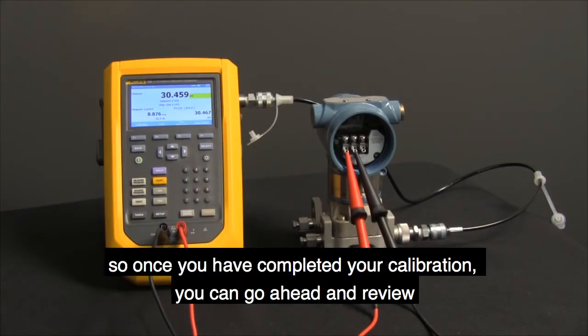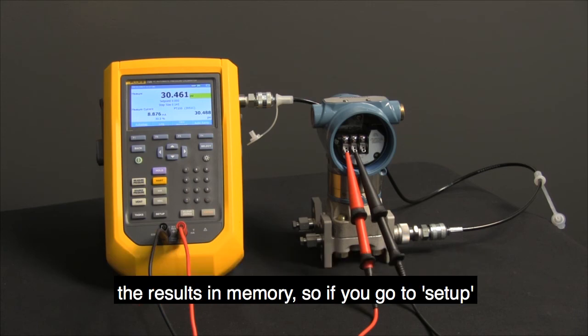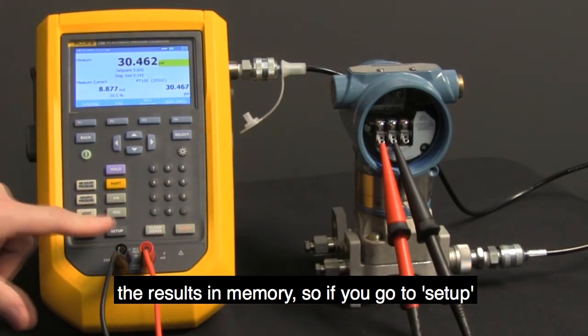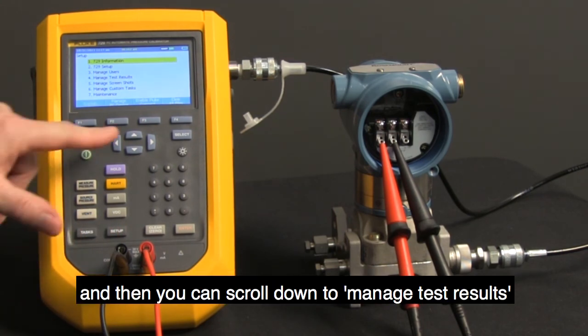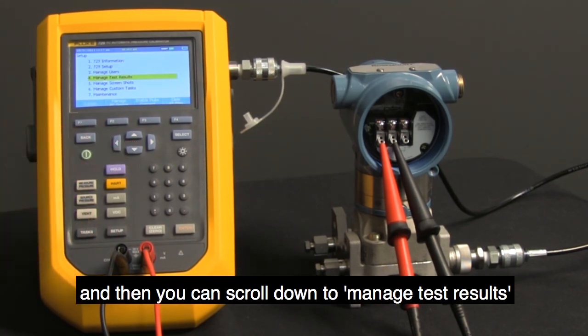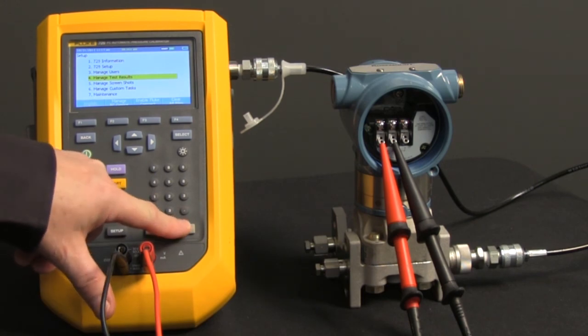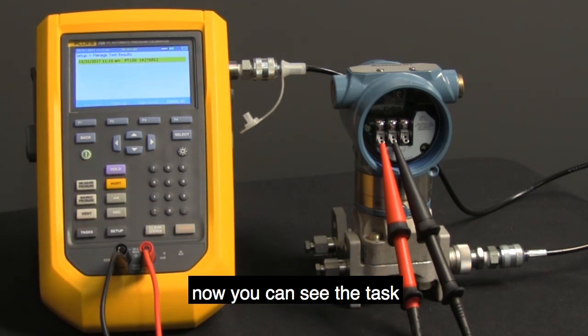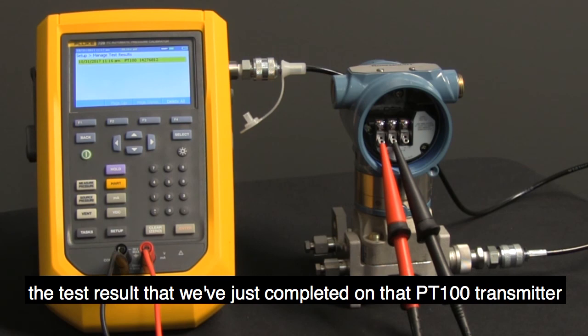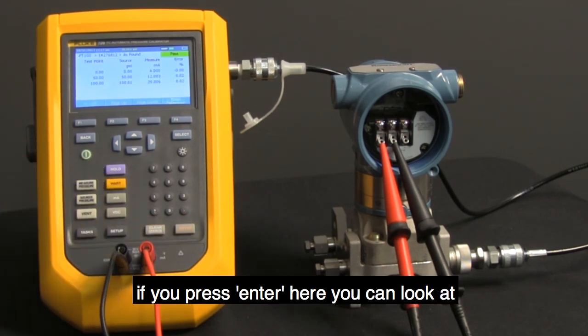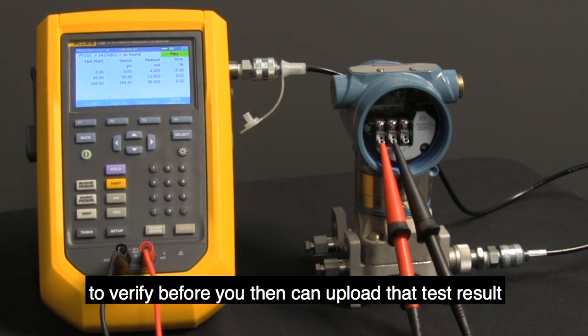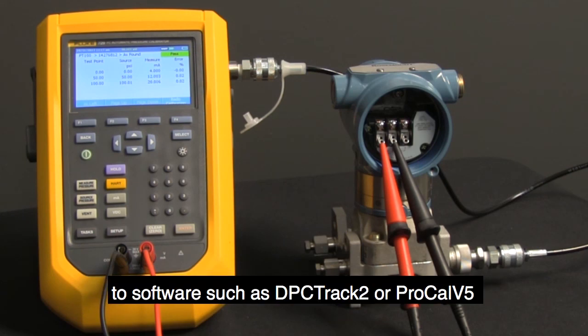So once you have completed your calibration, you can go ahead and review the results in memory. So if you go to Setup, and then you can scroll down to Manage Test Results, press Enter. Now you can see the task, the test result that we've just completed on that PT100 transmitter. If you press enter here, you can look at the actual test results to verify before you then can upload that test result to software such as DPC Track 2 or ProCal V5.